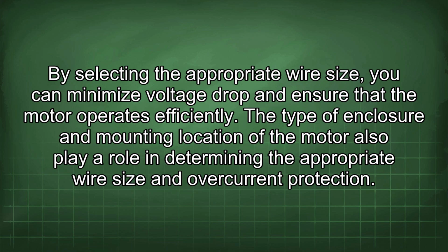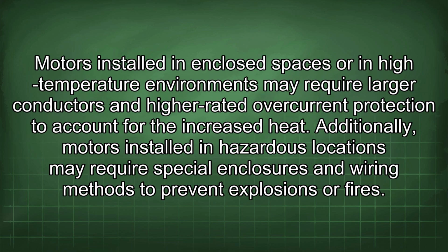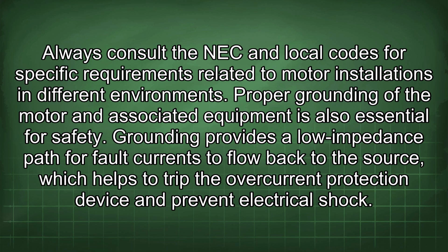The type of enclosure and mounting location of the motor also play a role in determining the appropriate wire size and overcurrent protection. Motors installed in enclosed spaces or in high-temperature environments may require larger conductors and higher rated overcurrent protection to account for the increased heat. Additionally, motors installed in hazardous locations may require special enclosures and wiring methods to prevent explosions or fires. Always consult the NEC and local codes for specific requirements related to motor installations in different environments.